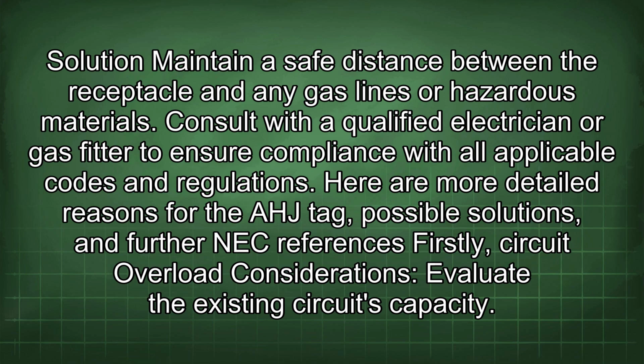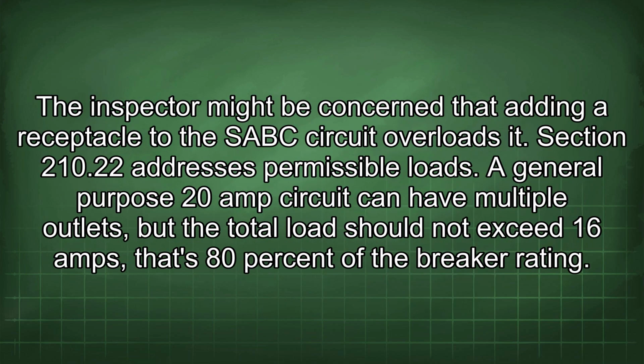Here are more detailed reasons for the AHJ tag, possible solutions, and further NEC references. Firstly, circuit overload considerations. Evaluate the existing circuit's capacity. The inspector might be concerned that adding a receptacle to the SABC circuit overloads it. Section 210.22 addresses permissible loads. A general-purpose 20-amp circuit can have multiple outlets, but the total load should not exceed 16 amps. That's 80% of the breaker rating.